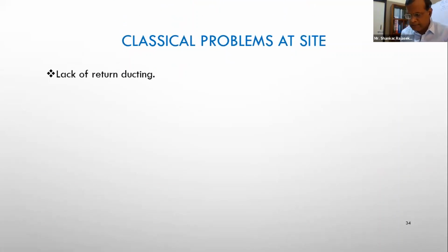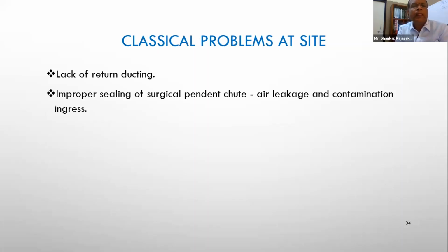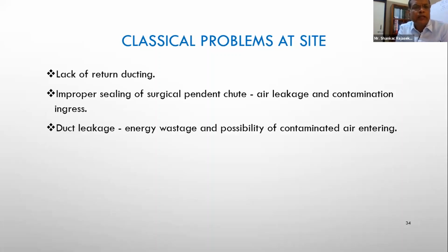ASHRAE very clearly says that wherever there is a need to maintain a differential pressure requirement, return ducting has to be there. You can't use a ceiling void as the return. Improper sealing of the surgical pendant chute, I think that's a repeat. Duct leakage. Duct leakage matters more than energy wastage, but it is looked at differently.